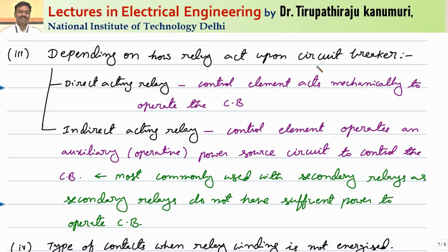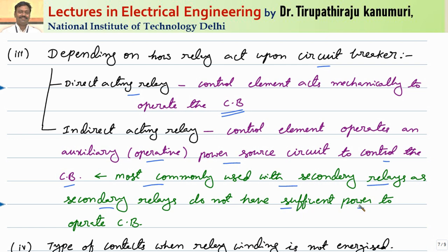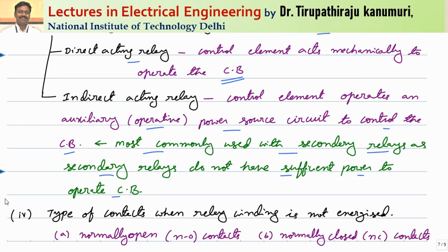Depending on how the relay acts upon the circuit breaker, there are two types. In a direct acting relay, the relay directly operates the circuit breaker with no intermediate circuitry. In an indirect acting relay, the control element operates an auxiliary power source circuit to control the circuit breaker — as seen in the basic structure of the relay. This is most commonly used with secondary relays, since instrument transformer burden should be minimal and the relay lacks sufficient power to directly operate the circuit breaker.